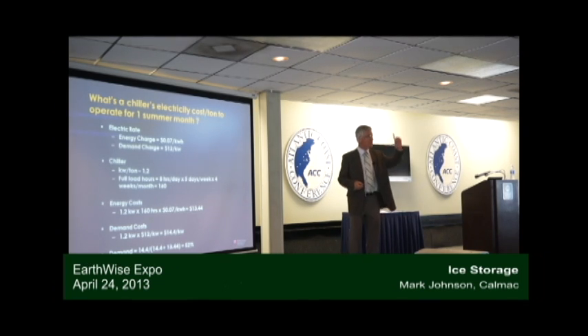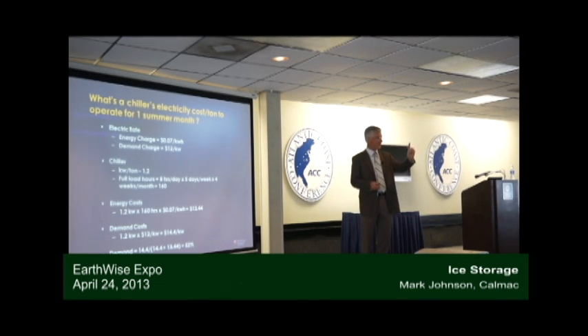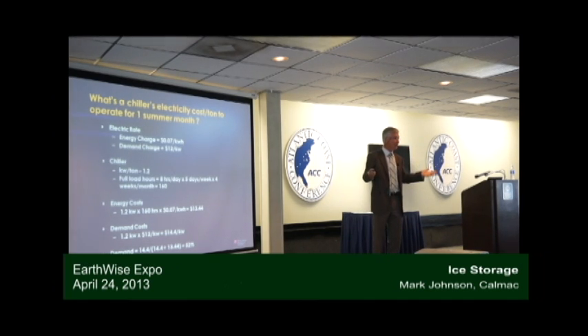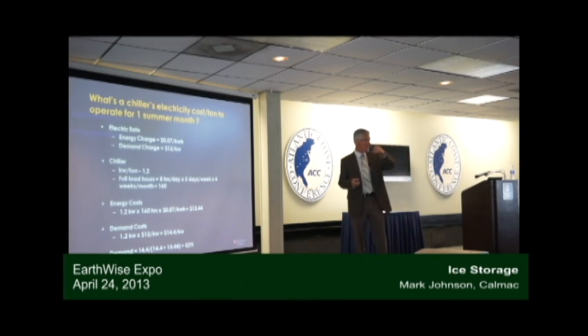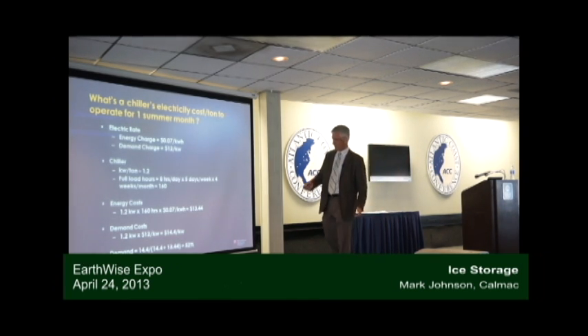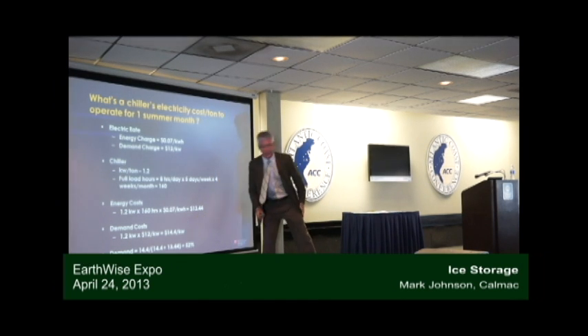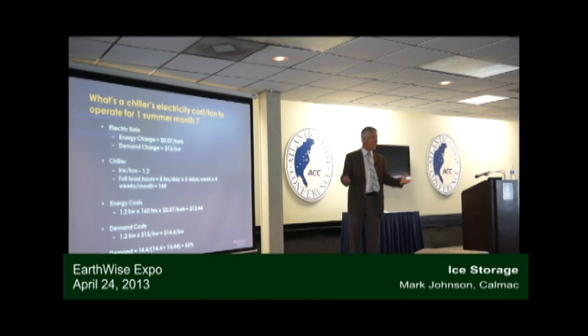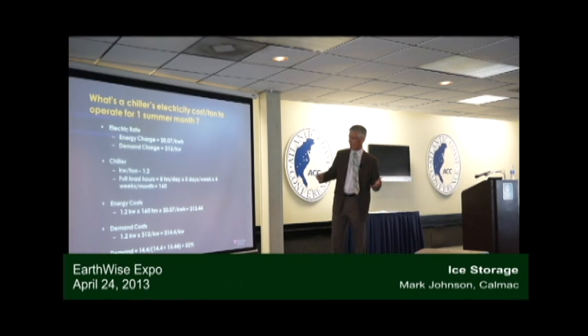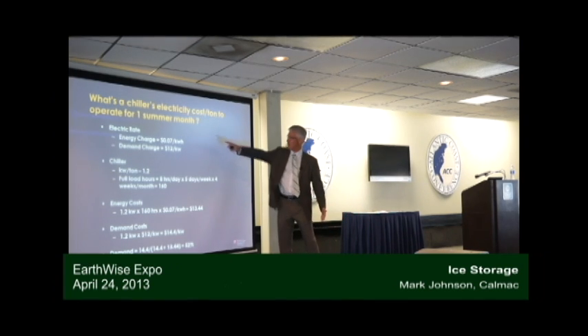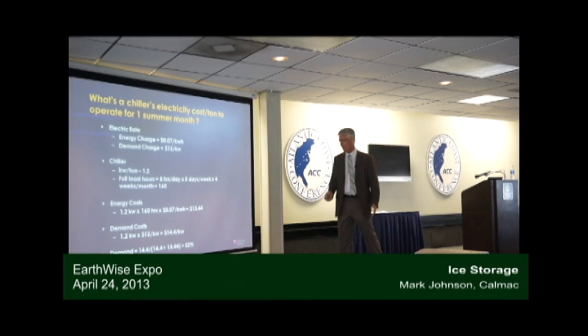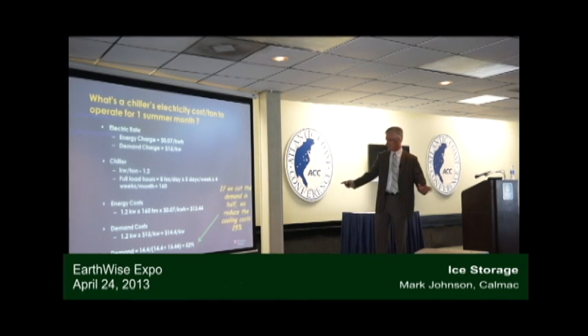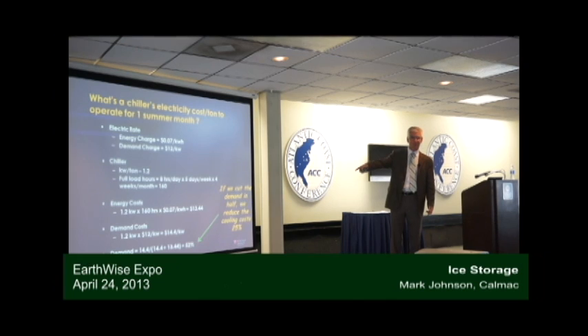If we operate that chiller just one hour and it sets our peak demand, will the chiller set the peak demand? Well heck yeah, it's running in the middle of the day. That's $14 for the demand. So you may think you're on a power rate of about 10 or 12 cents a kilowatt hour. You're not — you're on a power rate of 7 cents a kilowatt hour, $12 a kW. Your demand is 52% of your bill in this example.